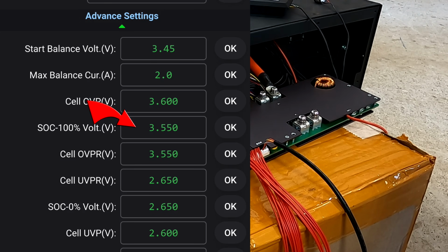Because as the user, we want to tell the BMS: as per my battery design, the battery is now full, please show 100%. We don't want to wait until we hit 3.65 volts or any other alarm voltage, like in the PACE or Seplos BMSs. This is actually pretty good - it has a separate entry here in the BMS where you can set your state of charge voltage.